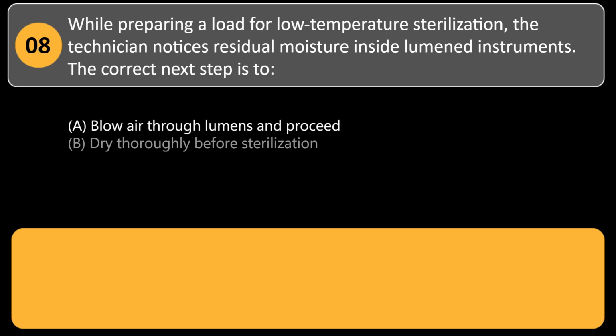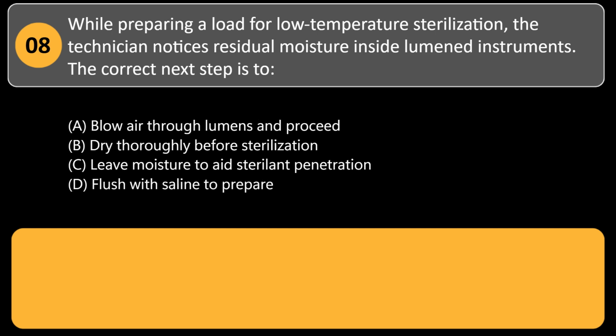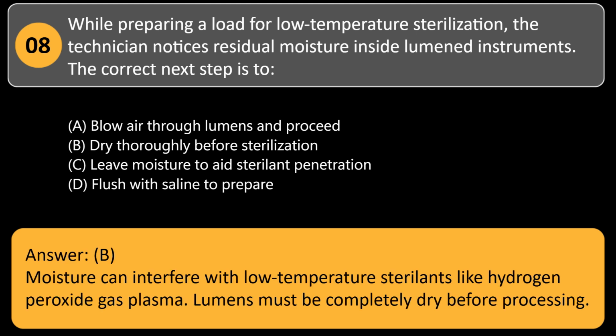While preparing a load for low-temperature sterilization, the technician notices residual moisture inside lumened instruments. The correct next step is to A. Blow air through lumens and proceed. B. Dry thoroughly before sterilization. C. Leave moisture to aid sterilant penetration. D. Flush with saline to prepare. Answer: B. Moisture can interfere with low-temperature sterilants like hydrogen peroxide gas plasma. Lumens must be completely dry before processing.